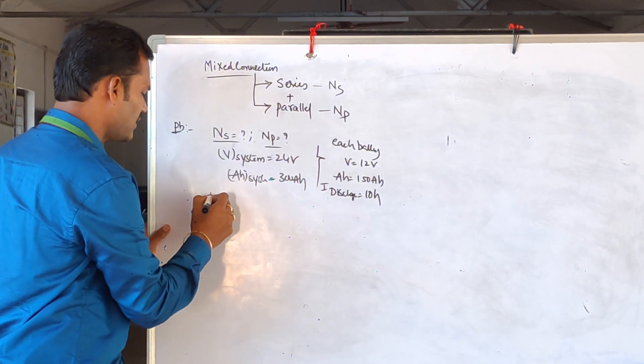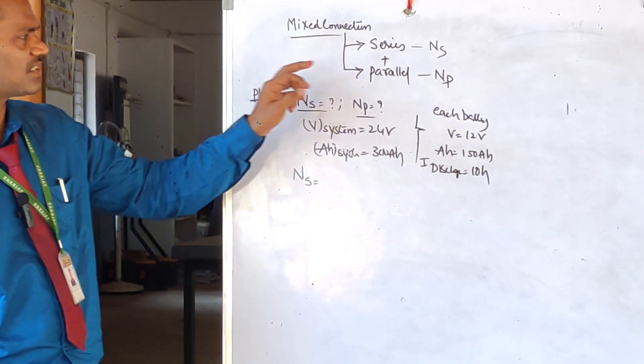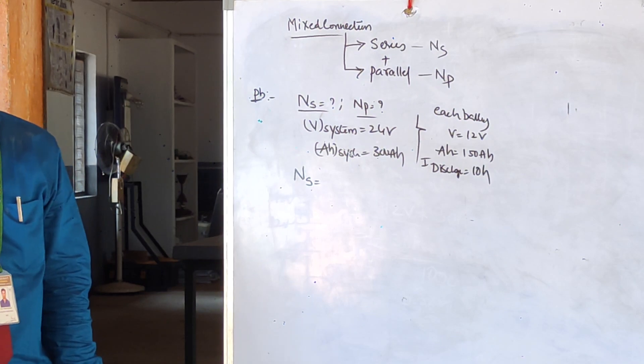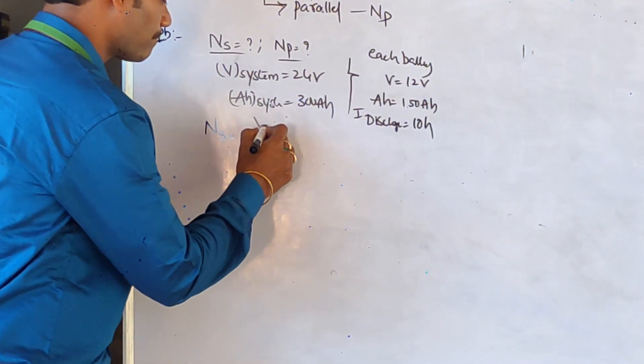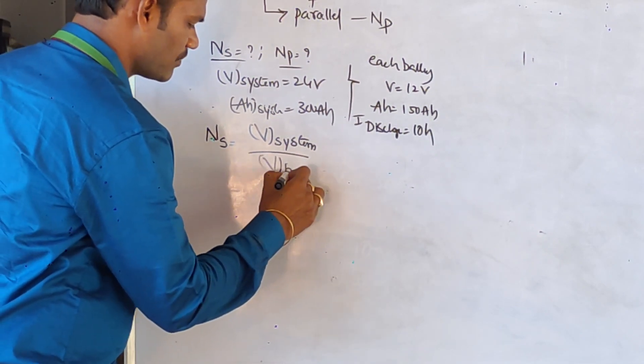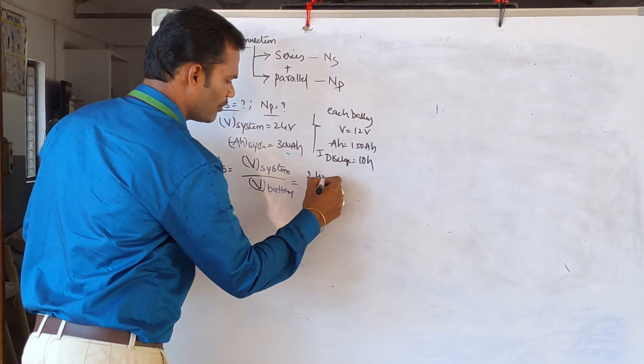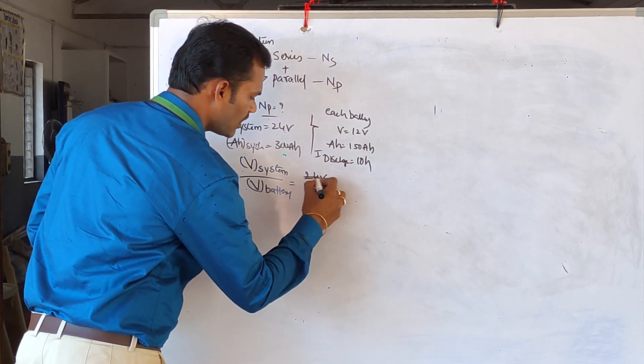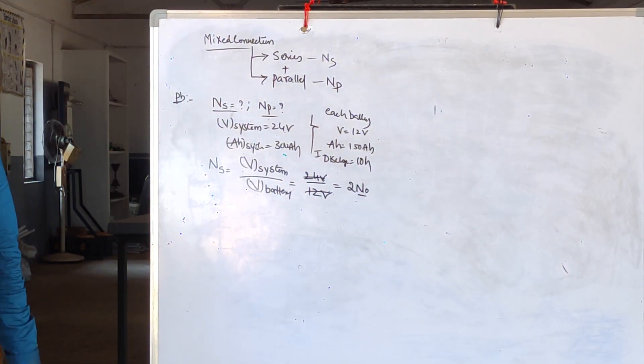First, let's calculate the number of batteries to be connected in series connection. The formula is: number of batteries in series equals system voltage divided by individual battery voltage. System voltage is 24 volts divided by individual battery voltage of 12 volts. Therefore, 24 divided by 12 gives us 2 batteries to be connected in series connection.